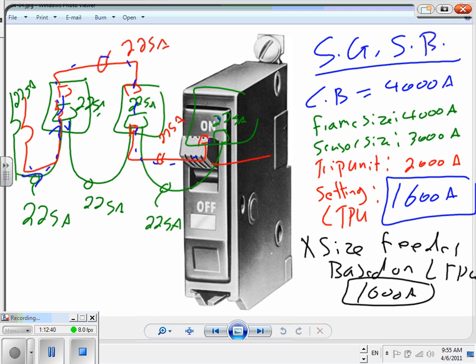With hospitals like Mayo Clinic that we did, we do all these settings, guys. You're going to be doing it as a designer. Come up with a setting from a 4,000 amp frame to a 1,600 amp, give the settings to the electricians, and size your conductors based on the 1,600 amp. That's why we have electronic circuit breakers, because you can tweak them. You can tweak them down, and you can get much more than what 240.6 can give you.